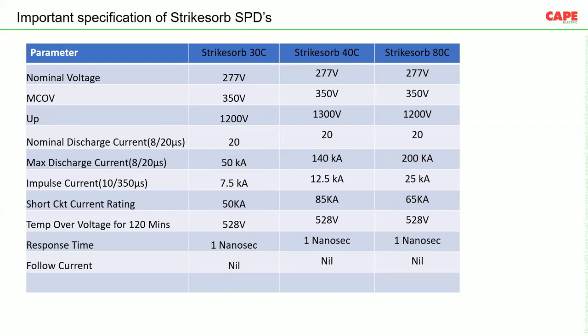That again is going to come in the future for the slides. Short circuit rating is 50 kiloamperes for Strikesorb 30, 85 kiloamperes for Strikesorb 40, and 65 kiloamperes for Strikesorb 80, and again, which is further tested with more rating also. TOV voltage, Strikesorb 30, 40 and 80 again are tested for 528 volt. Standard has recommended SPDs to be tested with 442 volts, but Strikesorb series SPDs are tested with 528 volt, which is much, much better.